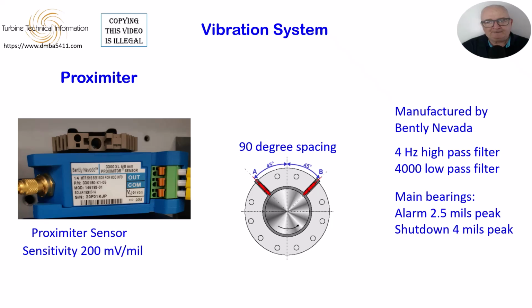The probes are buried inside the turbine bearings and are only accessible when building the turbine. These types of probes are also fitted to the generator and compressor bearings. Isolators, when fitted to these instruments, affect the signal sensitivity and must be taken into account when applying the alarm and shutdown levels.